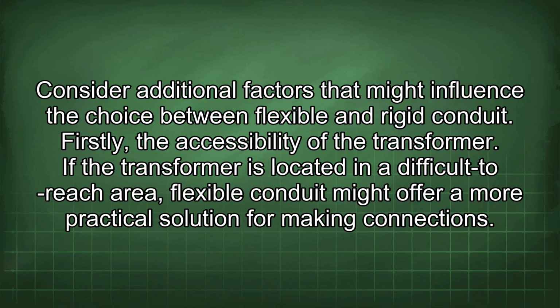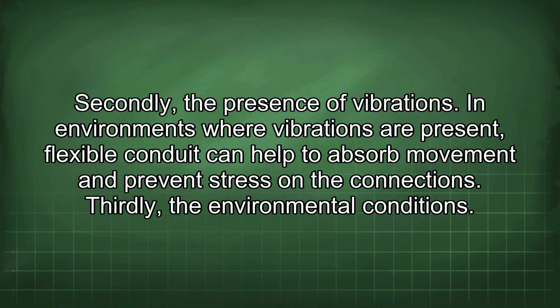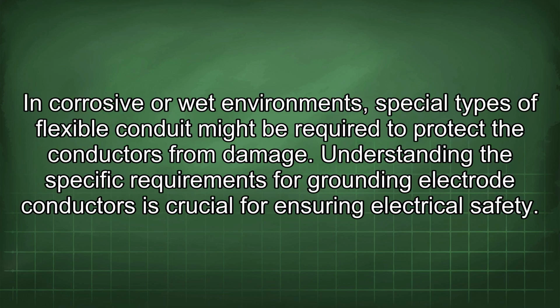Consider additional factors that might influence the choice between flexible and rigid conduit. Firstly, the accessibility of the transformer. If the transformer is located in a difficult-to-reach area, flexible conduit might offer a more practical solution for making connections. Secondly, the presence of vibrations. In environments where vibrations are present, flexible conduit can help to absorb movement and prevent stress on the connections. Thirdly, the environmental conditions. In corrosive or wet environments, special types of flexible conduit might be required to protect the conductors from damage.